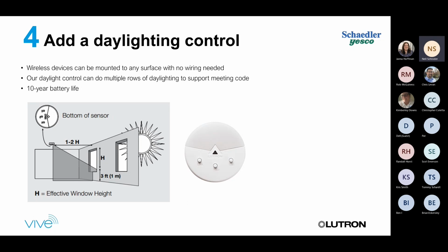Daylight sensors typically get mounted anywhere from one to two window heights away from a window, and they're tied to power packs or load controllers that are controlling lights along those perimeter windows. We generally don't want to use a daylight sensor to control power packs that are deeper into the space. We just want to take advantage of the natural light coming into that room right along those perimeter windows, and we can set different thresholds on how that works.